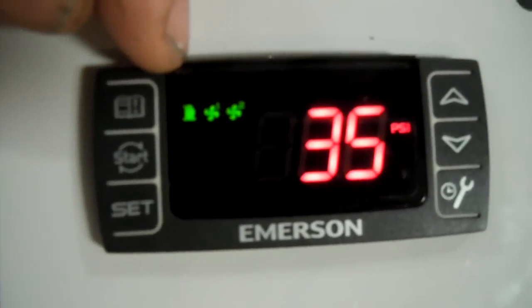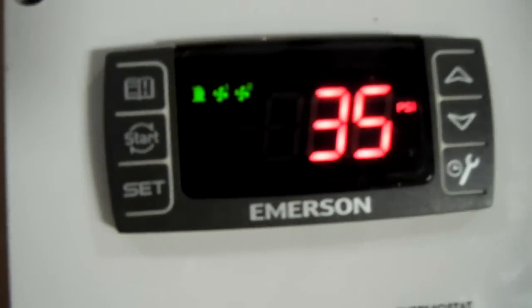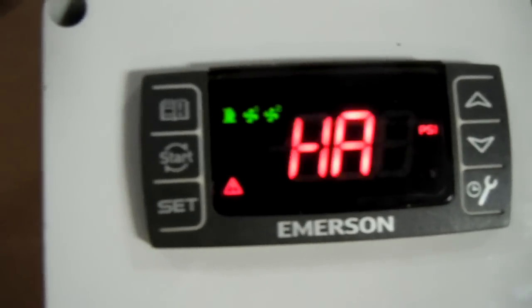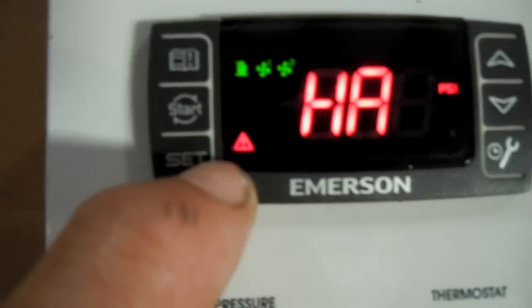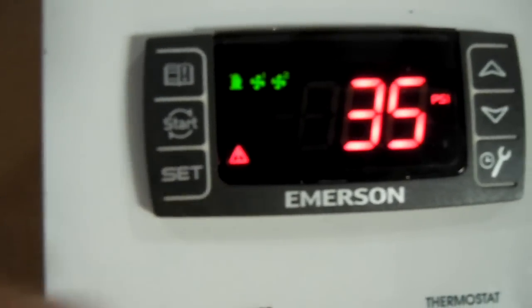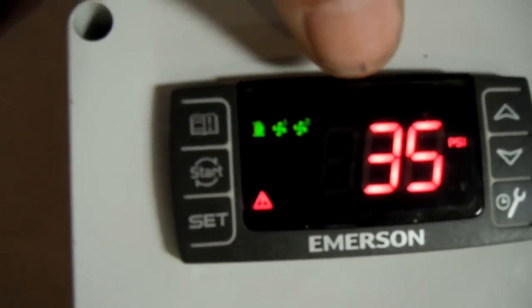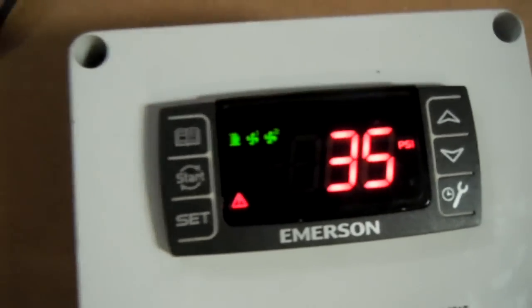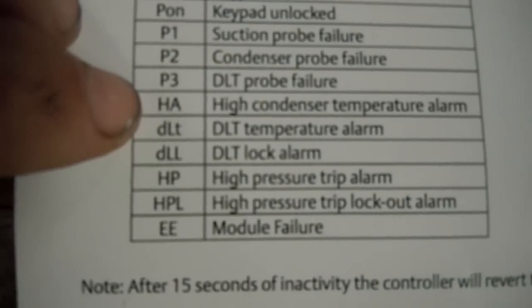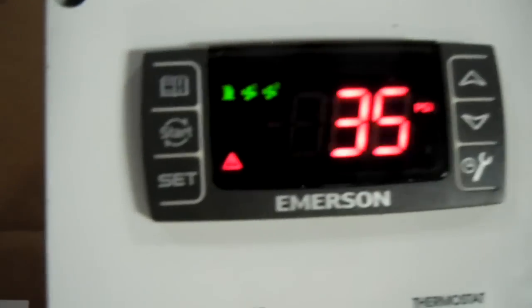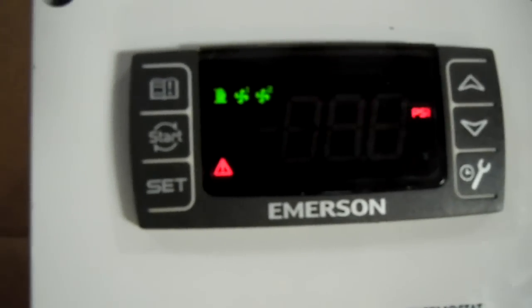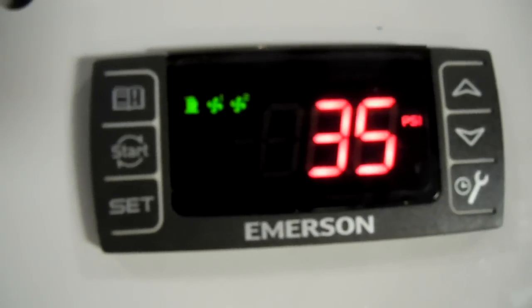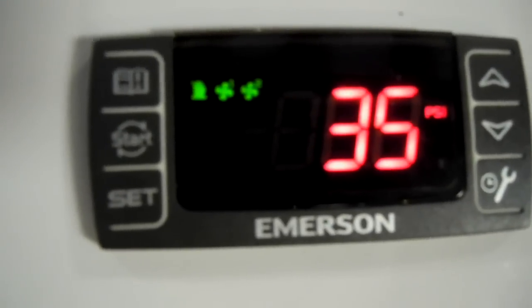And also, when the system goes into alarm, it'll come up with like a little red triangle and also it'll display the alarm. In this case, we have an HA, an HA means high condenser temperature alarm. When the condensing temperature goes back down, then the alarm will go out on its own.